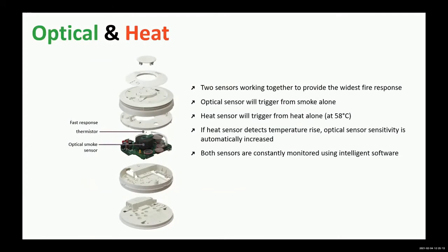We also have a couple of units which we introduced into the market over the last couple of years in relation to combinations of devices. So with the optical heat, it was there in this guise before, the multi-sensor, the EI2110. What we have here is probably the best unit on the market at the minute in relation to detecting any type of fire. You have 2 sensors working together to provide a wide range of fire responses. The optical sensor will trigger from smoke alone. The heat section will trigger from 58 degrees C.